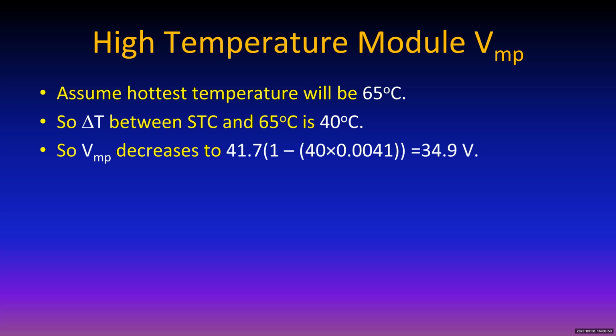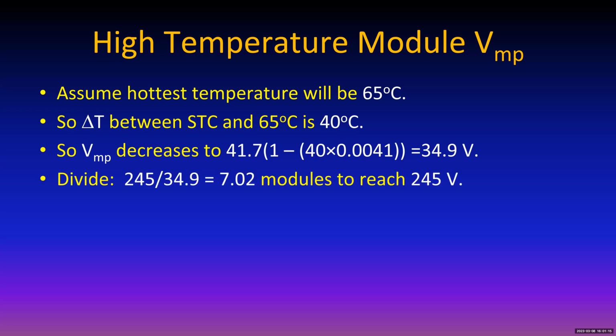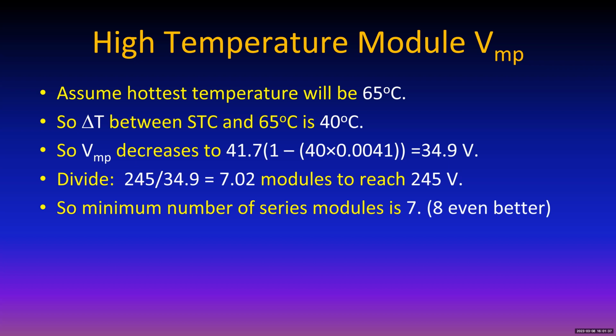And here's the formula you've been waiting for. 40 degrees and the coefficient for the maximum power point voltage, again negative, but this time we're subtracting from 1 instead of adding to 1 as we get warmer. And so we're dropping from 41.7 to 34.9, which means 7.02 modules to reach 245 volts. So if you put 7, you're asking for trouble maybe 1% of the time. So if you want to be really sure you don't mess up here and stay within that window, you're going to put in 8. Okay.